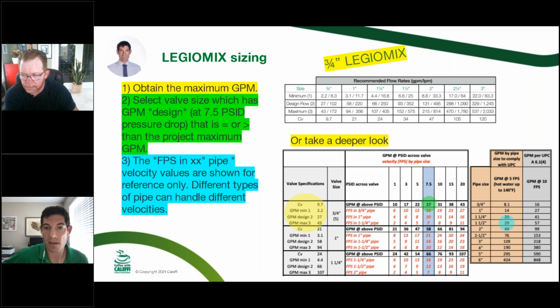That's pretty high. So 16 at 3/4, one down is 10 at 1 inch pipe. And then we're starting to get a little bit more reasonable with 1.25 inch pipe at 7 feet per second. In this case, everything's going to be sized well if we do a 3/4 inch Legio mix, but going all the way over to the blue on the very right, we still want to keep that 1.25 inch trunk piping.